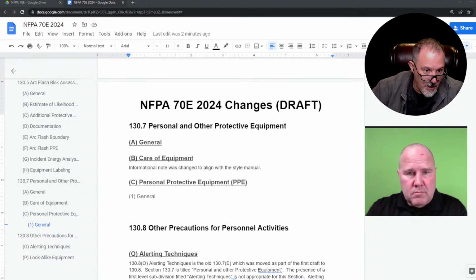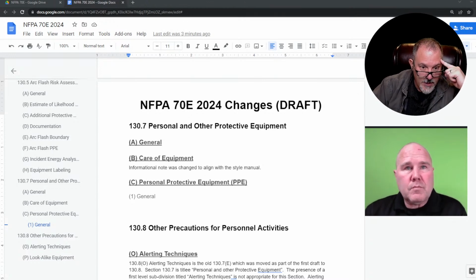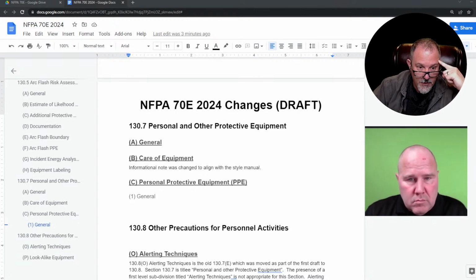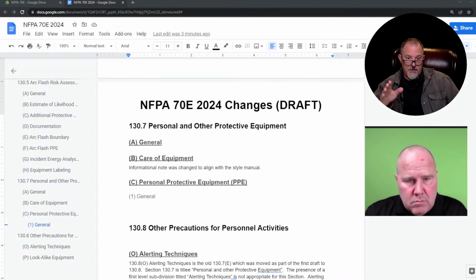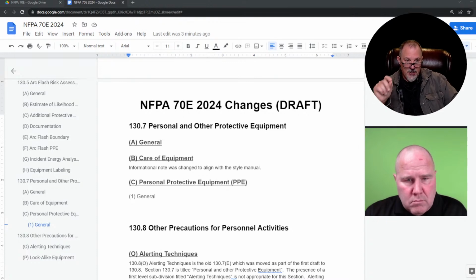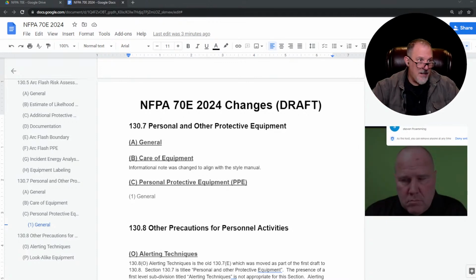All right. So this is the previous example of a risk reduction method in item 1 of this informational note. It lacked clarity and may have created confusion. The first revision deletes the reference to the secondary side of a low voltage transformer mounted in the equipment because the text was confusing. The intent of this risk reduction example is for the employee to get an indication of the absence of voltage before coming in contact with a contact type test instrument.